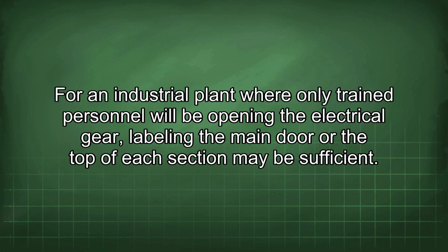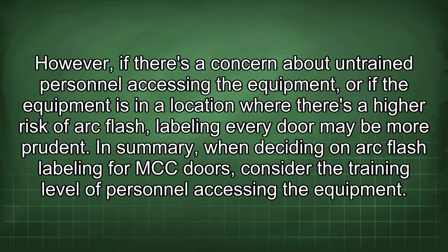For an industrial plant where only trained personnel will be opening the electrical gear, labeling the main door or the top of each section may be sufficient. However, if there's a concern about untrained personnel accessing the equipment, or if the equipment is in a location where there's a higher risk of arc flash, labeling every door may be more prudent.